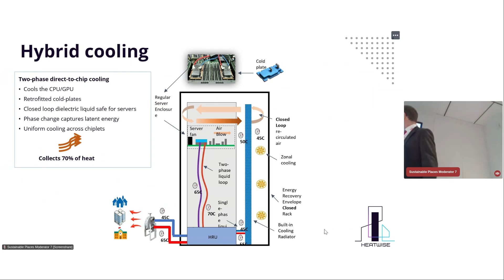Here I'll try to wrap up how the system works. We have a closed cabinet, and inside there's a radiator which takes up the air heat. It's conveyed into the HRU, the heat rejection unit, which preheats the cold supply. The cold is 65 degrees, and with that we cool the CPU on-chip, which sends back 70 degree vapor. After some loss, at 65 degrees we give it out to the building, and the building gives us back 45 degrees.